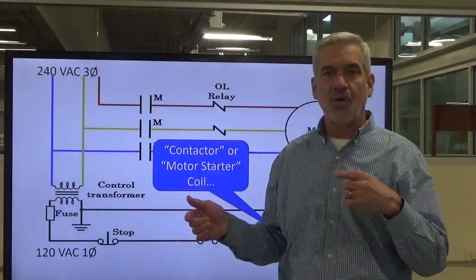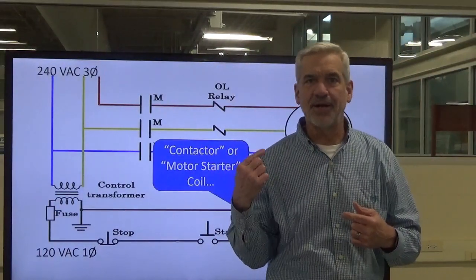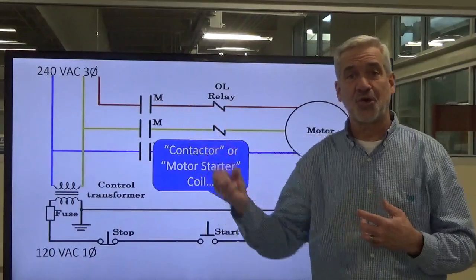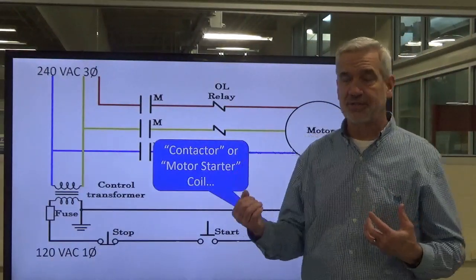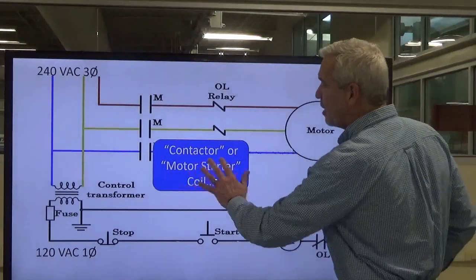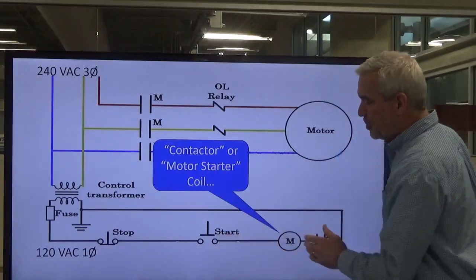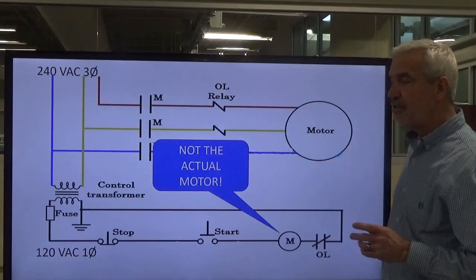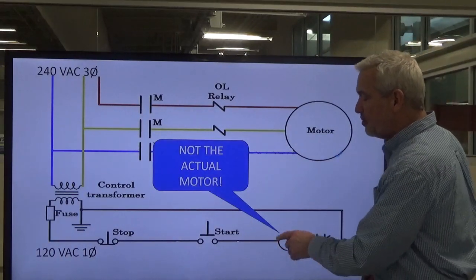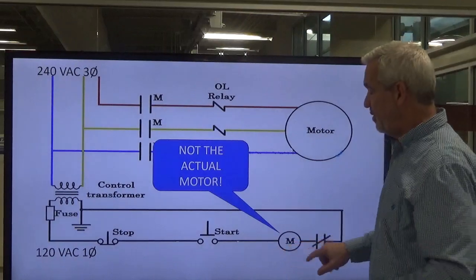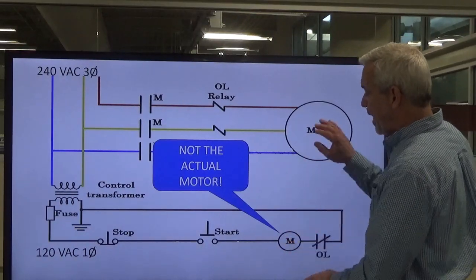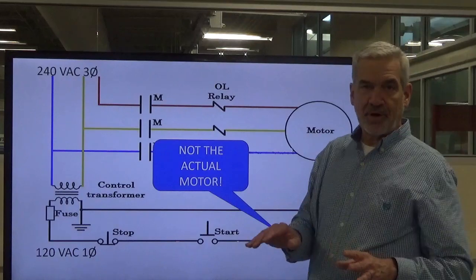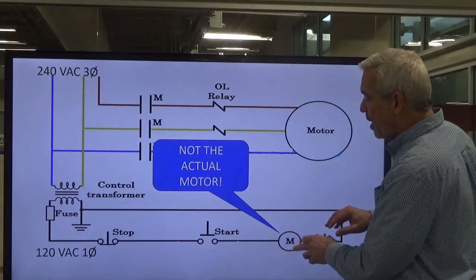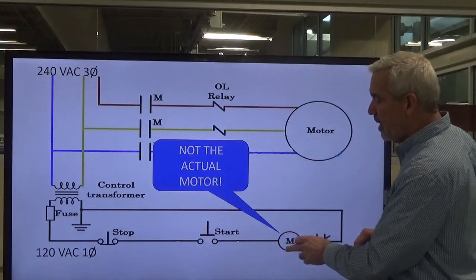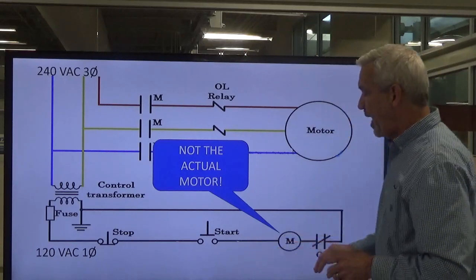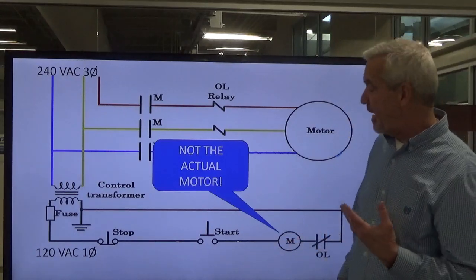There's that word again, coil, where we're talking about one piece of wire wrapped around and around and around. We create a magnetic field that's going to attract some piece of laminated steel, okay? So that's what the motor contactor does when we energize the coil. Now, I want to be real certain to let you know, in the control circuit, this is not the motor, okay? The motor and the motor contactor are separate, okay? The contactor coil here is simply in the control circuit, and we energize that and we create that magnetic field.